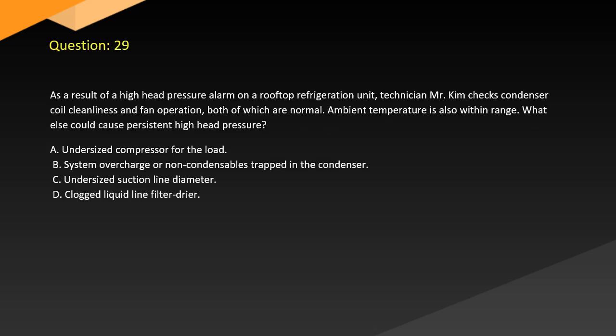Question 29. As a result of a high head pressure alarm on a rooftop refrigeration unit, technician Kim checks condenser coil cleanliness and fan operation, both of which are normal. Ambient temperature is also within range. What else could cause persistent high head pressure? A. Undersized compressor for the load. B. System overcharge or non-condensables trapped in the condenser. C. Undersized suction line diameter. D. Clogged liquid line filter dryer.